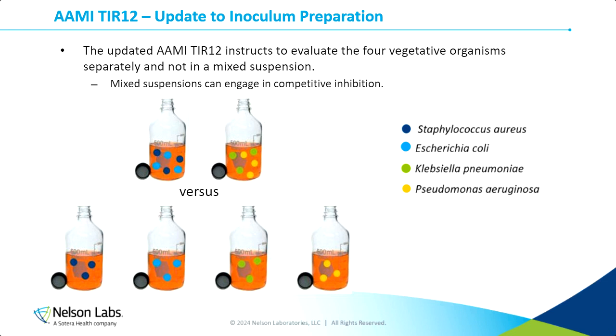The concern here is that mixed suspensions can engage in competitive inhibition, which may result in a lower microbial recovery count and a better log reduction calculation at the end. That may be due to the competitive inhibition and not necessarily the disinfection process. So AAMI TIR12 states to test these four organisms individually in separate inoculum suspensions. Historically they were done in groups of two, with S. aureus and E. coli grouped together, and K. pneumoniae and P. aeruginosa grouped together. But now the recommendation is to evaluate them not in those mixed suspensions.